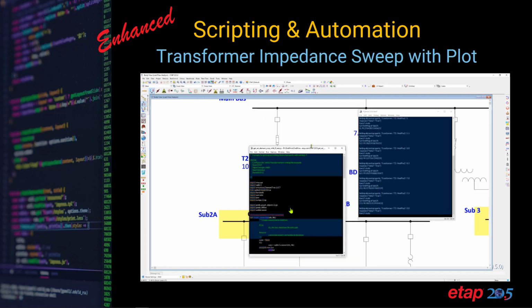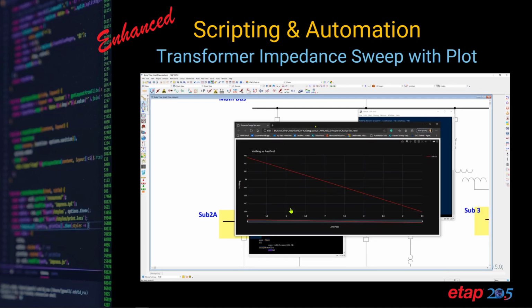The script runs a load flow computation at every 0.5 step, then reverts the value back to 7.9 when finished. You can use the plot analyzer to see impedance versus voltage magnitude. As expected, as impedance increases, the voltage drop on the transformer increases, which you can use to right-size the transformer.